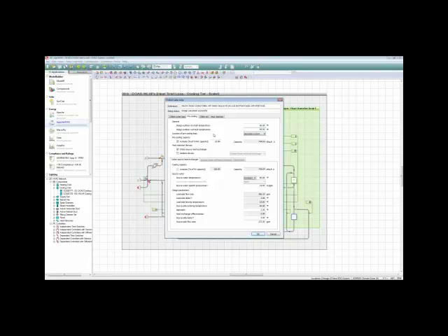So you might have a separate cooling tower or some other device, or in this case a water source heat exchanger that is set up to pre-cool that return water from the coils or chilled ceilings or whatever it's coming back from, and address that load as much as it can before that even goes to the chiller set.